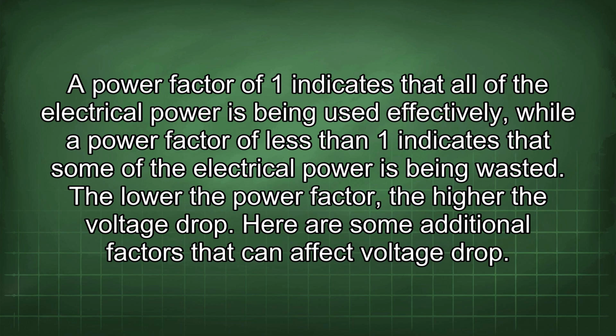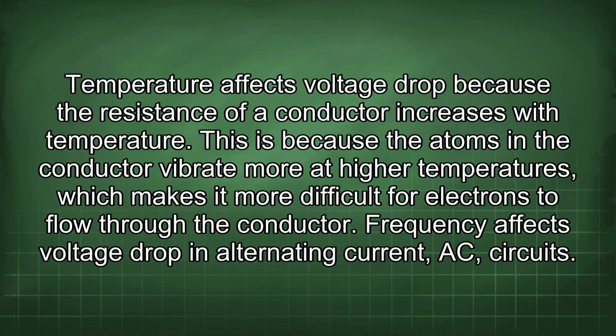Here are some additional factors that can affect voltage drop. Temperature affects voltage drop because the resistance of a conductor increases with temperature. This is because the atoms in the conductor vibrate more at higher temperatures, which makes it more difficult for electrons to flow through the conductor.